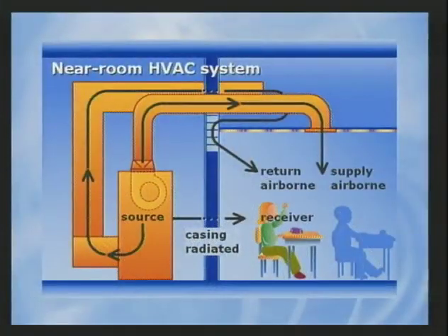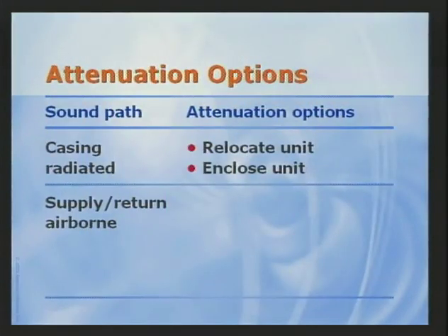The major problem with this approach is that it will most likely inhibit access to the unit for servicing. It's generally best to move the unit so that it isn't over the occupied space. This allows the use of a wall to block the casing radiated sound. It also allows for longer duct runs, which can be a benefit when attenuating supply and return sound paths.